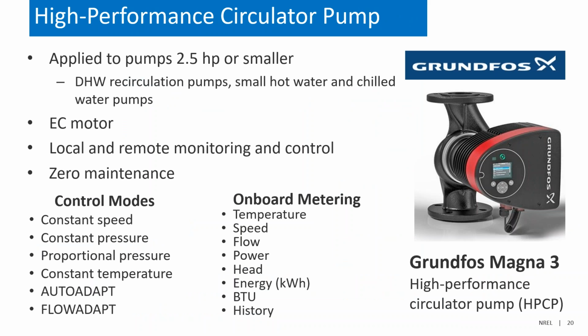So just a quick introduction to high-performance circulator pumps. A circulator pump is essentially a small pump that has the motor rotor, the pump impeller, and the support bearings that are all sealed inside of the pump. Sometimes these are called inline pumps, as those pump flanges that you'll see there are directly mounted in line with the piping system.